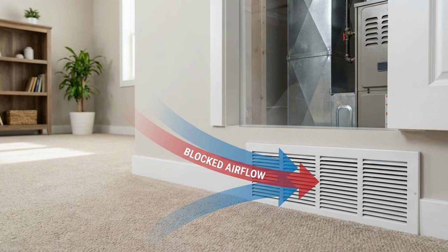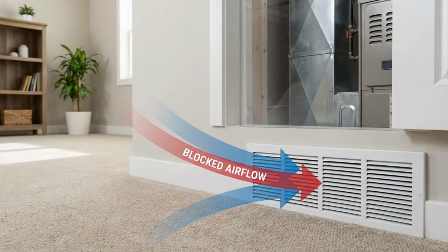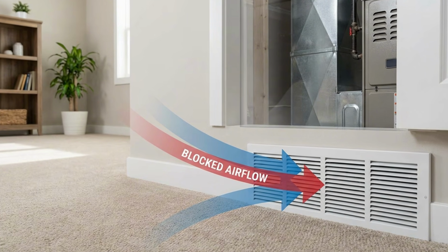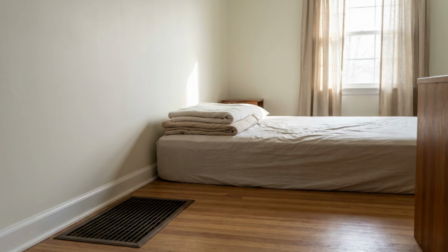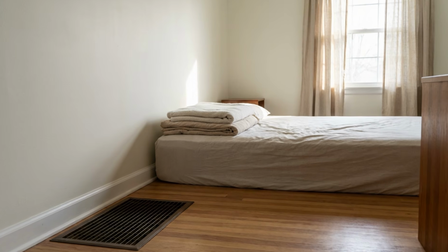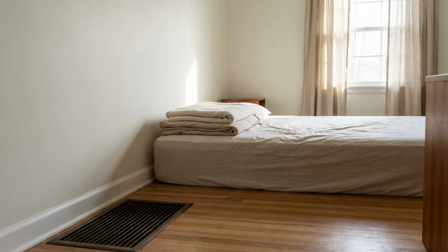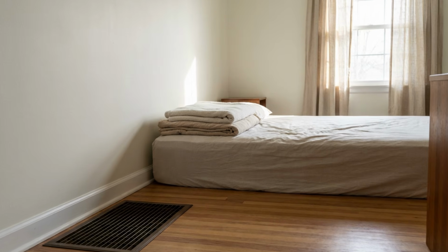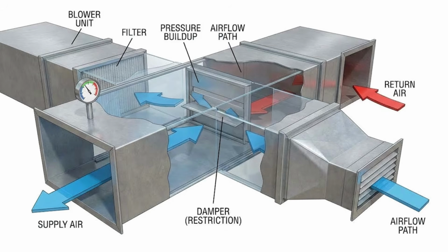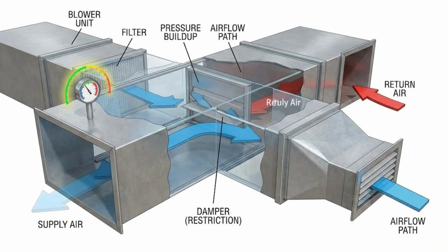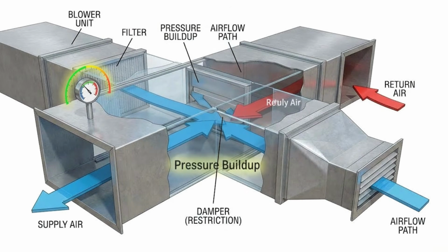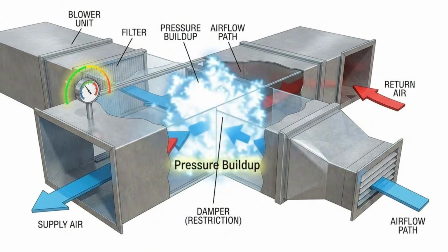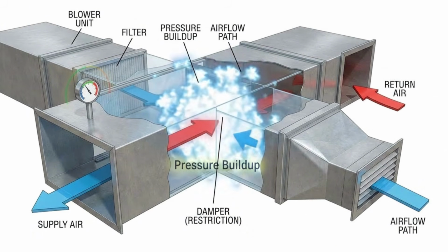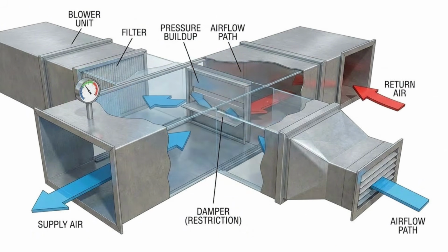Mistake 2. Closing vents to save energy, and why it backfires. This one is everywhere. You have a guest bedroom nobody uses, so you close the vent. Seems logical, right? Less space to cool, lower bills. Here's what's actually happening. Your heating and cooling system was designed, or should have been designed, to move a specific amount of air at a specific pressure.